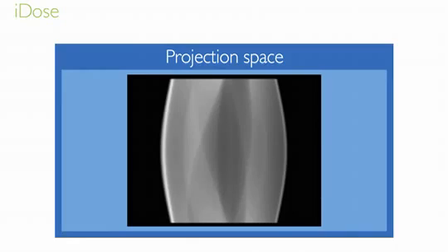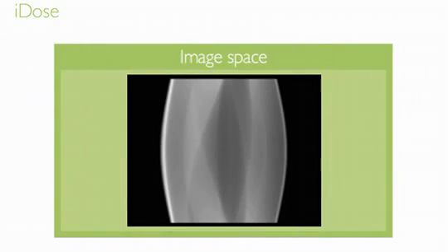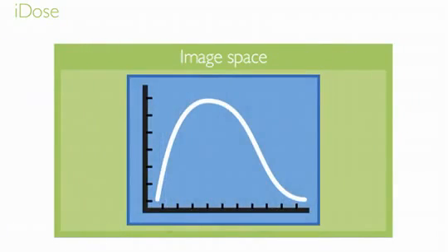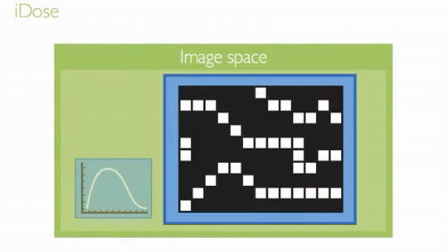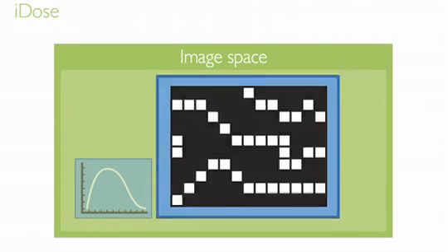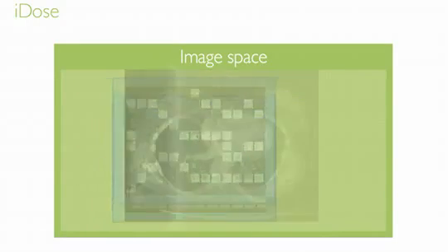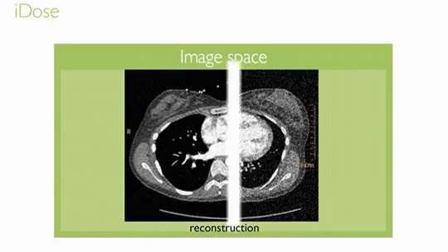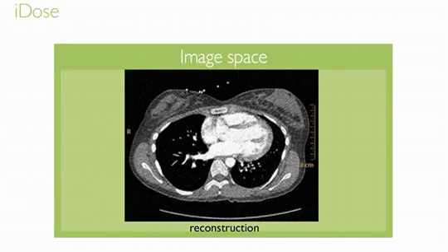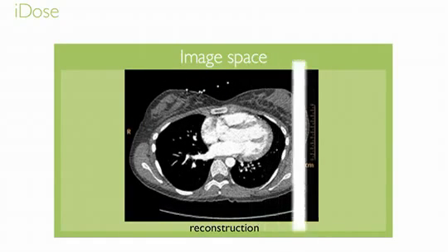These projections then transition to the image space where two models are created. The noise model is a statistical representation of the noise in the data. The anatomical model is a representation of the clinically relevant features of the dataset. Combining this information, iDose iteratively removes the noise while retaining clinical data.